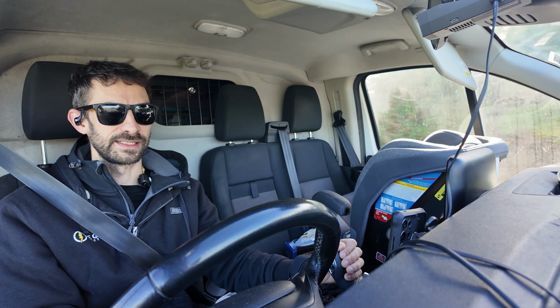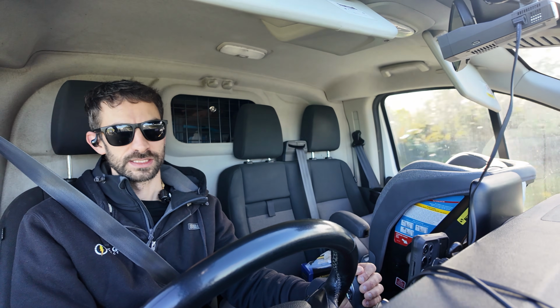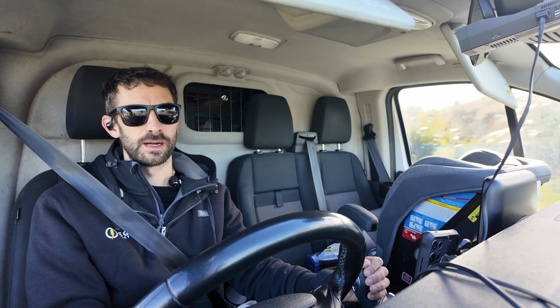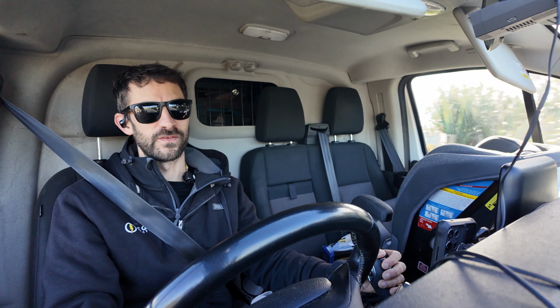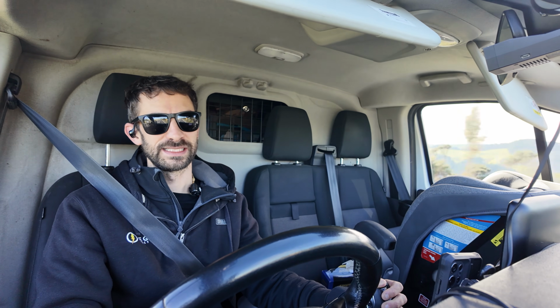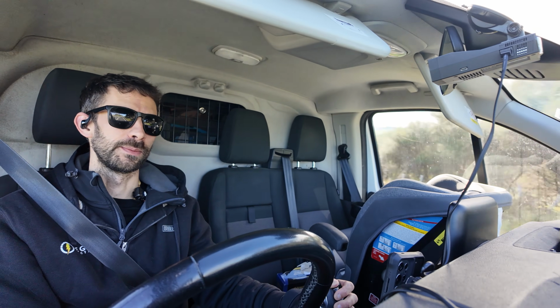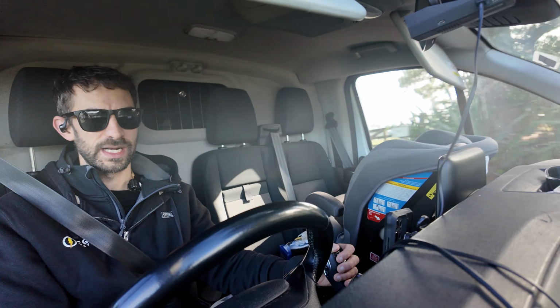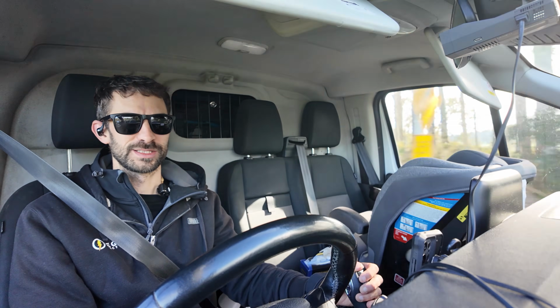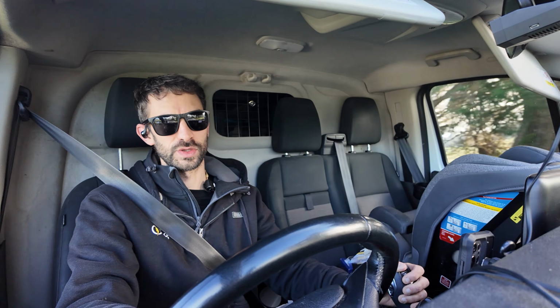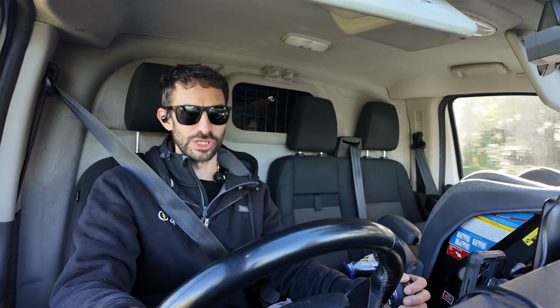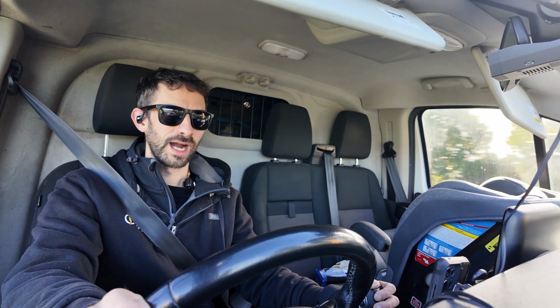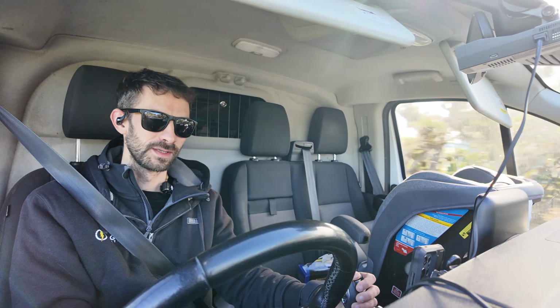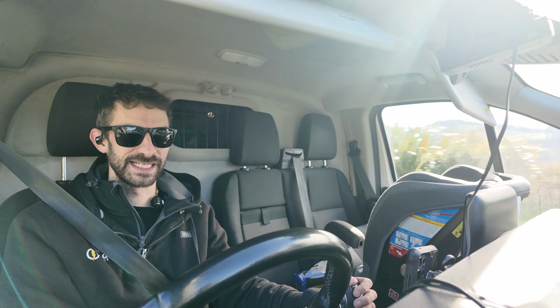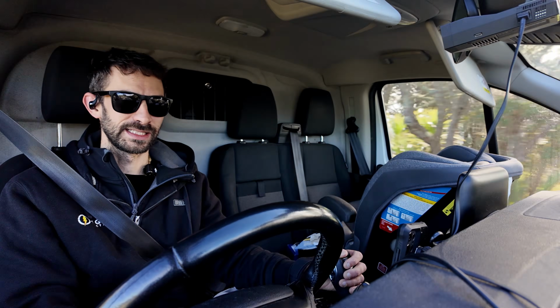The electrical system in New Zealand is designed under a two faults philosophy. So the idea is for harm to occur, there must be two faults. So another thing where only one fault can cause harm is a transposed phase and neutral conductor. But I don't think of that in the same category, because if you transpose the phase and neutral, somebody made a mistake when they terminated the wires and somebody failed to test that. So the solution to that is for electricians to do their job properly, for linesmen to do their job properly, for electrical inspectors to do their job properly. Just test your work. And there are cases of phase neutral transposition. People get punished for it from time to time, but we solve that one by testing. It's a really easy thing to do. If you can't do that test, you shouldn't be an electrician.